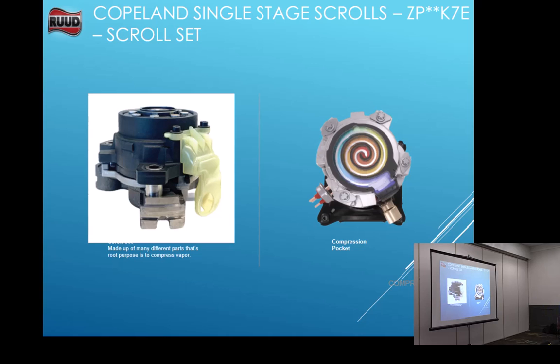This is what we kind of talk about here. This is our suction funnel that we have on our compressor. Oh, I forgot a part here. Pass this around, guys. Let you play with it. If we don't have our airflow right, this is what happens to our compressor. Okay? You've heard me talk about airflow and everything. That compressor there ran 7 seconds. If we don't have our airflow right and our charge right, that is what happens. They do not pump liquid. It got in there with liquid, and that's what happens when it tries to pump liquid. It just comes apart.